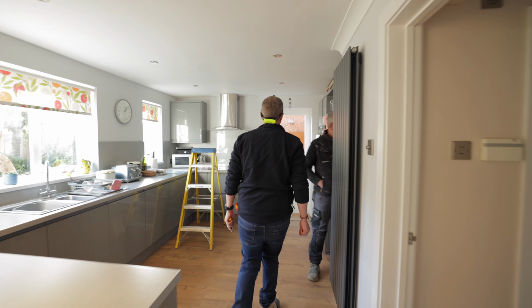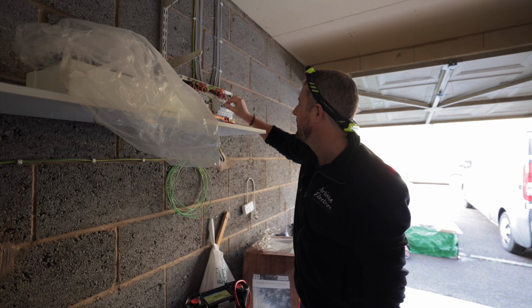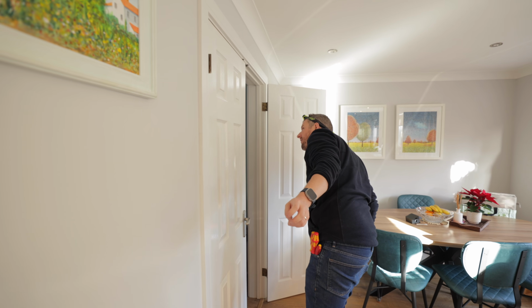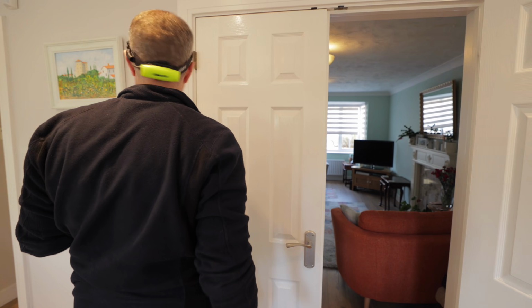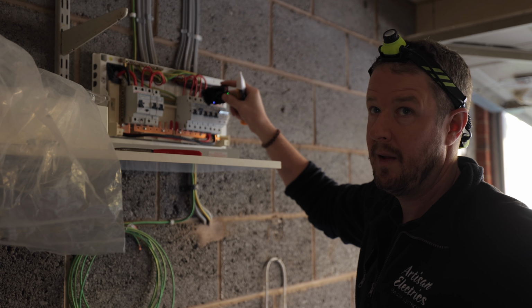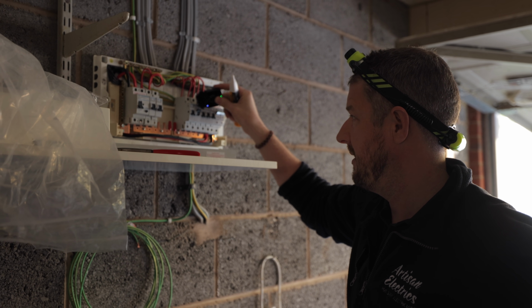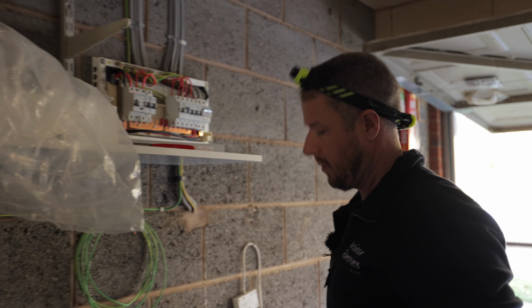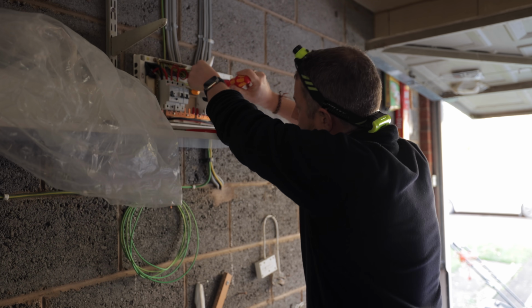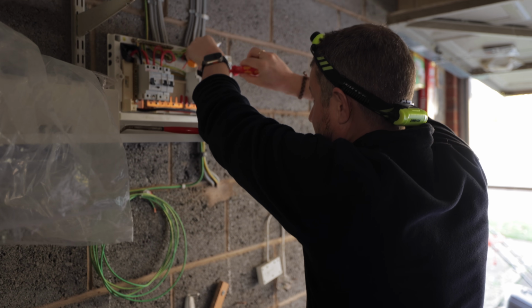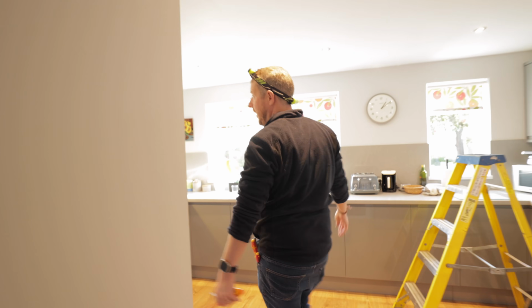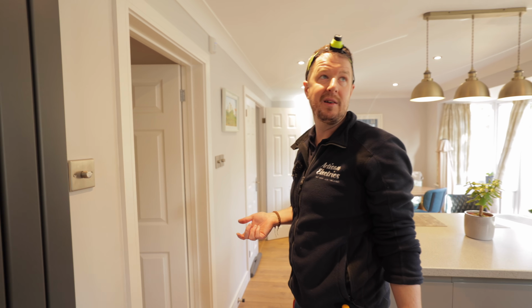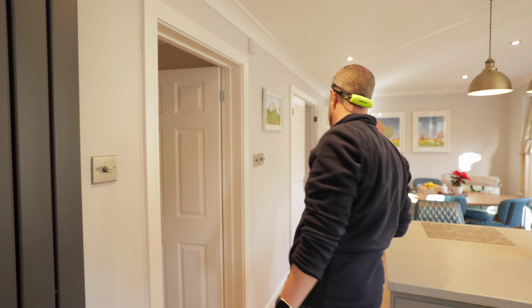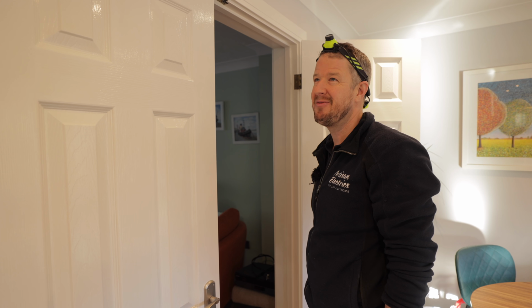Okay, let's check that circuit breaker, because it might just be a dodgy circuit breaker. Okay, let's try that. Okay, yeah, they're on, but they're very dim. Oh, and now everything's flickering again. This is so bizarre. So the flickering is coming from the circuit breaker. This circuit breaker is definitely a bit dodgy. What I'm going to do is turn this one off, swap into this one for a moment just as a test, and see if that solves the flickering. And they're not, everything is fine. So that circuit breaker is clearly on the blink, it's on its way out, which is why you've been having problems with lights flickering. Doesn't really solve the problem of the voltage on the ceiling for me, but let's check it now and see if it has gone away or not.